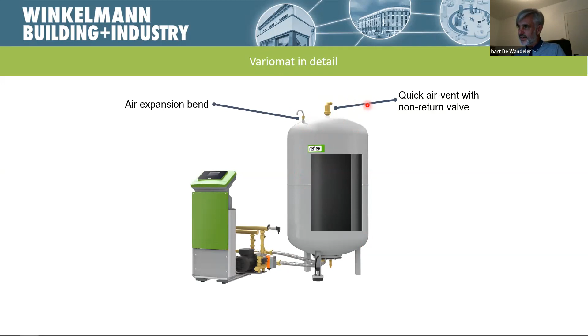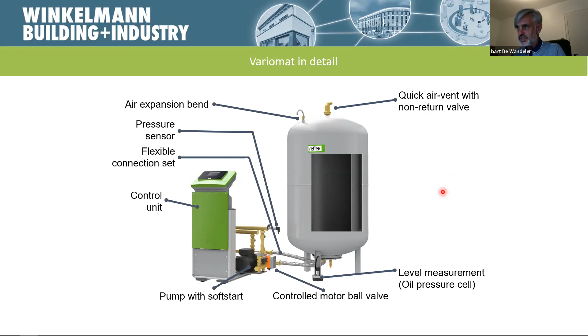We have, of course, the control units. We have pumps with soft start, so they are not aggressive. If we start the Variomat system, it will not go to full power. The pump will start smoothly, which also makes a kind of safety for your system, so that you don't get very hard, heavy shocks in your closed system when you have a pressure drop, for example. We also have the control motor valve from Belimo, where we can switch and also regulate the degassing a little bit, and we can switch to let water in or to pull or push out water. And of course, like in the compressor system, we also have the level measurement, so we can see the level status of the vessel here on the screen, or you can send those values to a BMS system or an alarm system, to protect and to monitor from a distance.